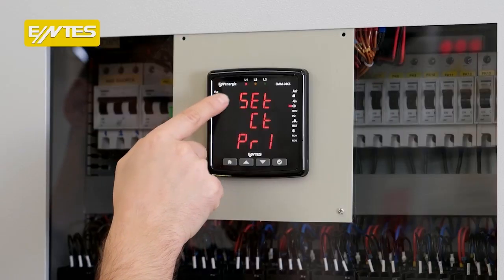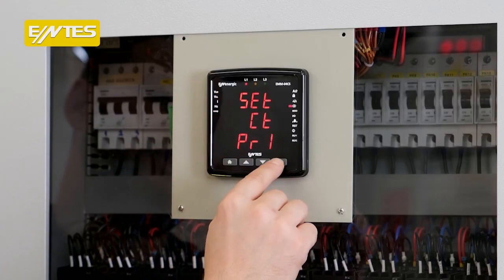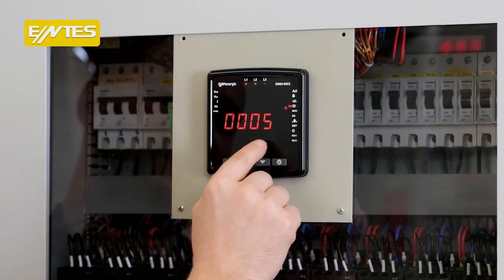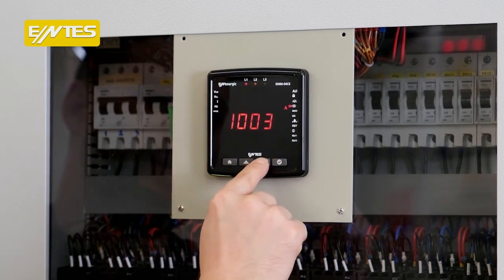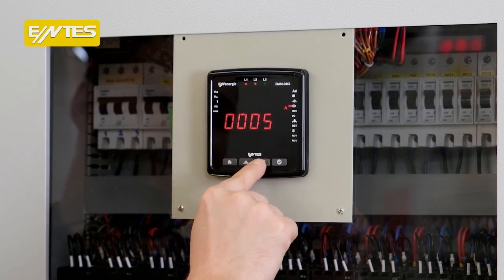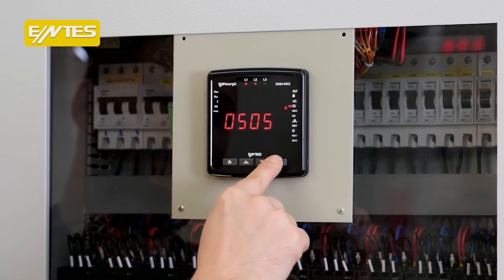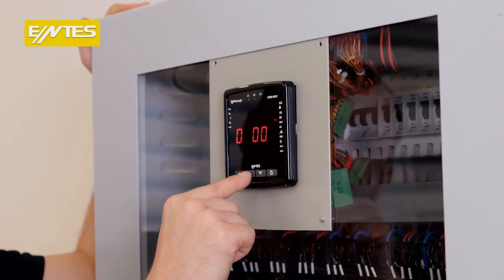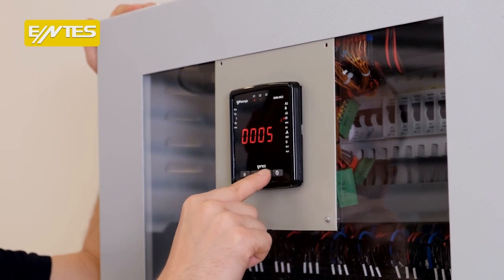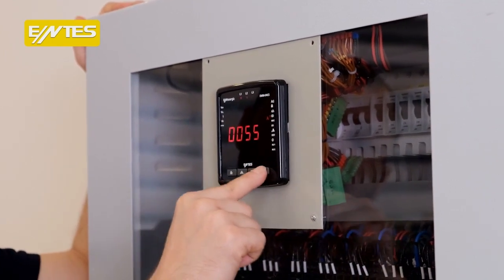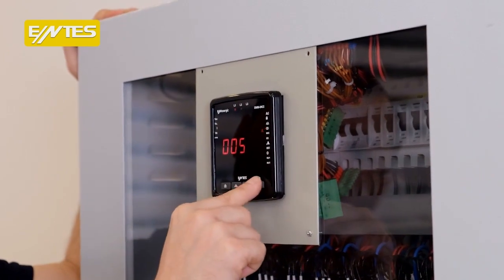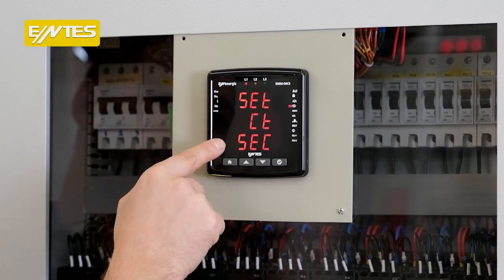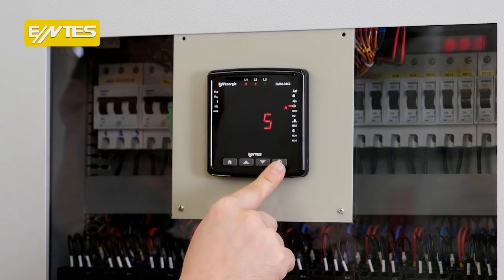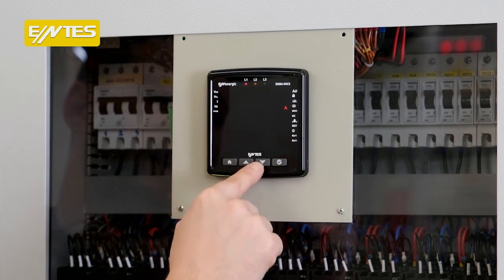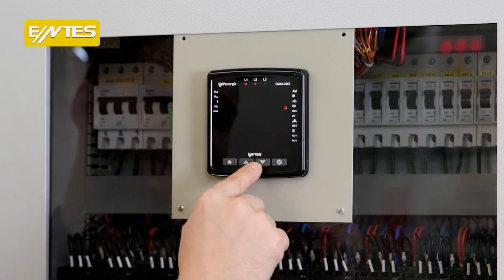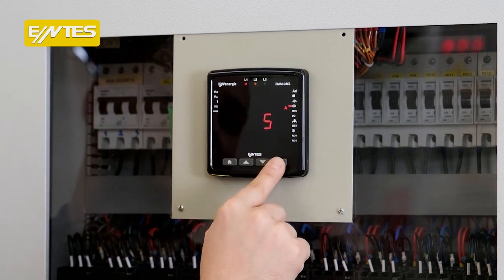Look, it says enter CT primary here, so we need the primary of the current transformer. Here is a 4-digit display. If we use a current transformer of 5 to 1000, it will be equal to 1000. If a current transformer of 5 is used for 500, this place is made 500. We will use a current transformer of 50 to 5 here, so we made this 50. I approved. It says to enter CT secondary again. The device supports 5 amp and 1 amp secondary input. Because it is 50 to 5, we chose our 5 amp.